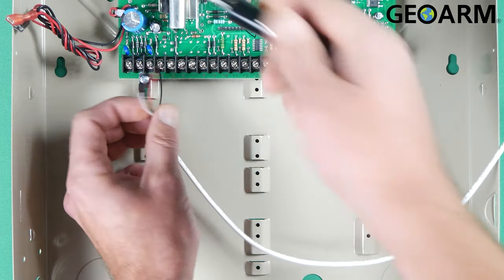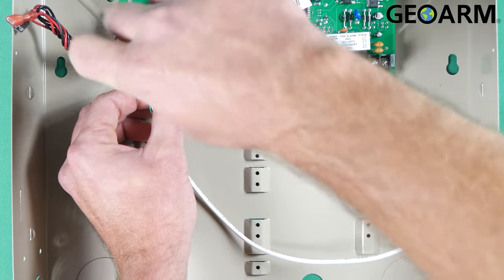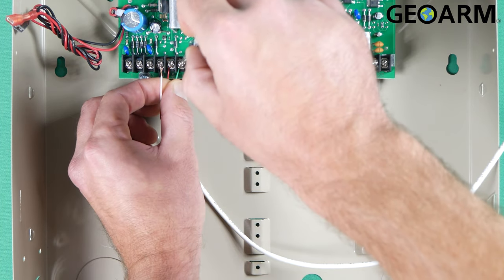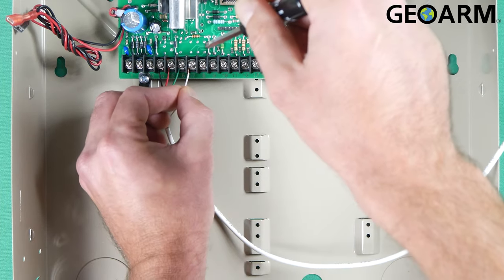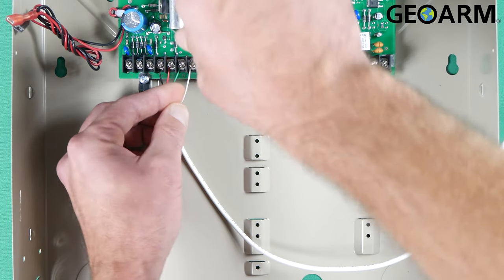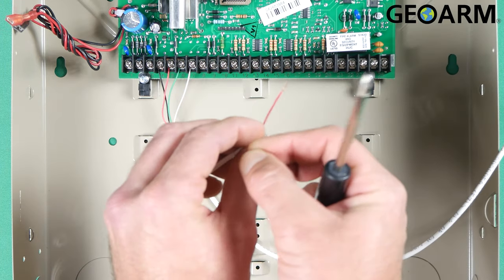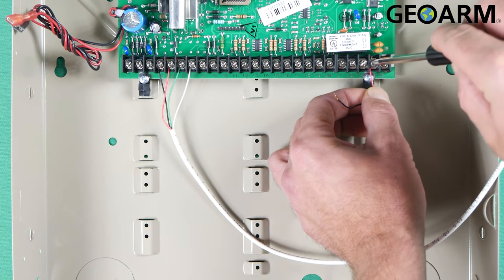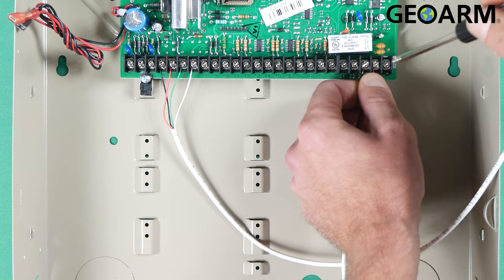Black is going to go to terminal 4, which is ground. Then we're going to go red — our positive power — to number 5. Then we're going to go green to number 6, and then we are going to go white to number 7. Once we've done that, we're going to go ahead and make our communication connections at tip and ring. We are going to be going red to 24, or ring, and then black to tip, or 23.